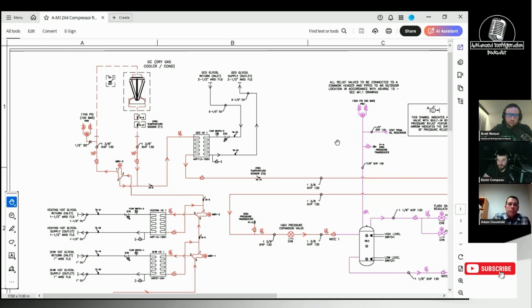Yeah, I would like to say that splitting the condenser would be advantageous, and it should be in theory. It's just a matter of getting the control where, when that upset does occur, the system can recover or doesn't go back and forth several times. Are you guys pumping the split side out when you do that? Yep. How are you accomplishing the pump out with a high pressure expansion valve? No, just a very small orifice solenoid valve. Okay. Where are you going with the pump out? Are you going to the flash tank?